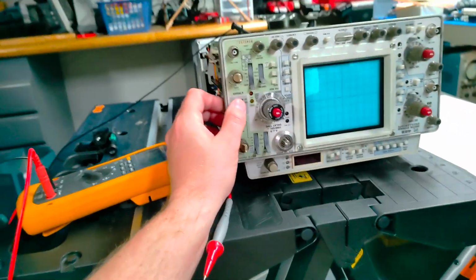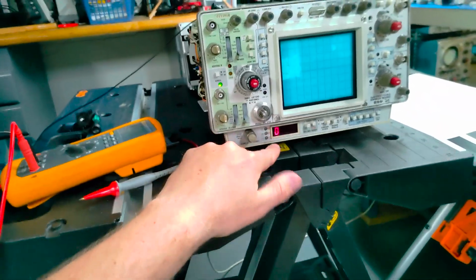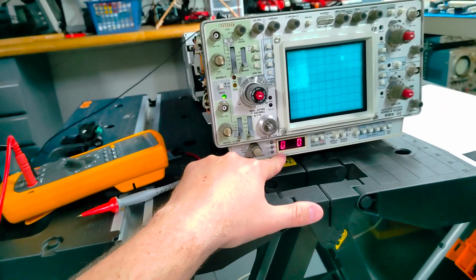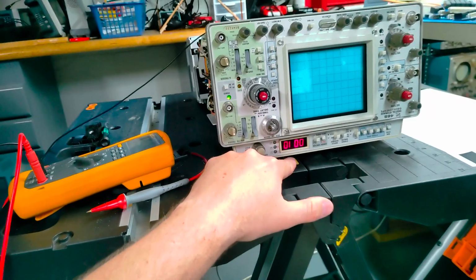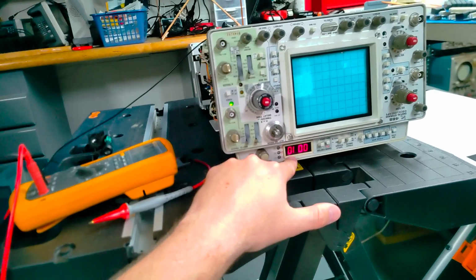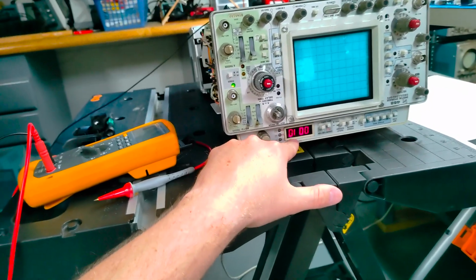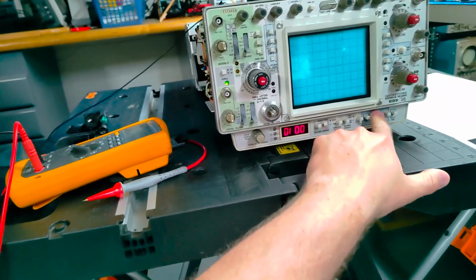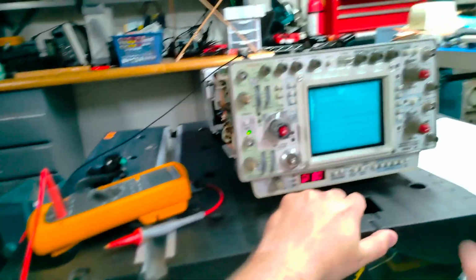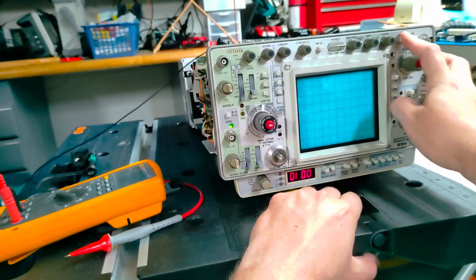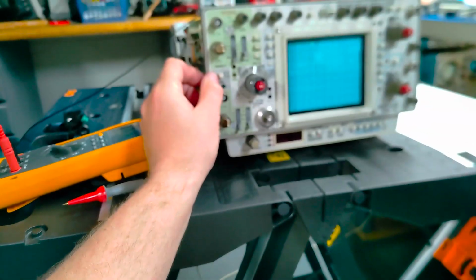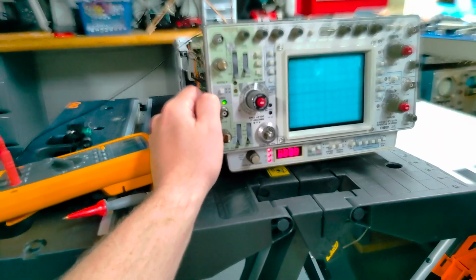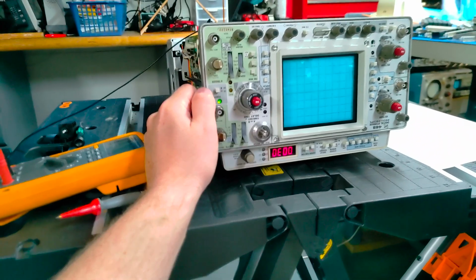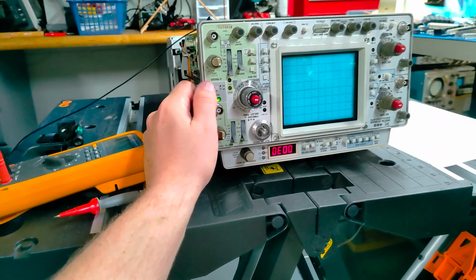When you turn it on, you'll get some funny readings on the digital readout, or the digital section. This is upside down, but it's reading code 10. And what would happen is sometimes this would actually pass and it would go into normal operation. You could use these buttons and stuff, but there was never any output on the screen, even like beam find or anything. And if I turn it off and turn it back on, it might give us a different code. Yeah, this time it's giving us 30. So I've seen 10, 20, and 30. And every once in a while, it'll boot all the way, and you'll be able to use these buttons even though nothing's on the screen.